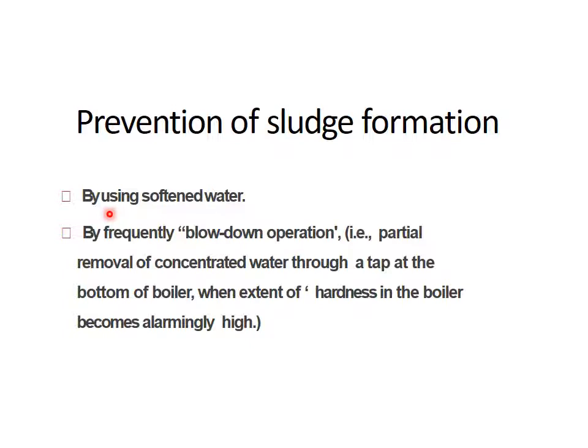Prevention of sludge formation: if we use soft water, sludge formation will not occur. By frequent blowdown operation — i.e., partial removal of concentrated water through a tap at the bottom of the boiler when the extent of hardness becomes alarmingly high — and by continuously removing the sludge from the bottom of the boiler using a tap, we also increase the efficiency of the boiler, because we are continuously removing sludge formed within the colder part of the boiler.